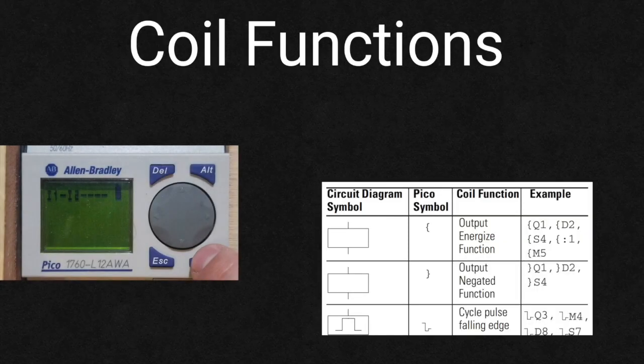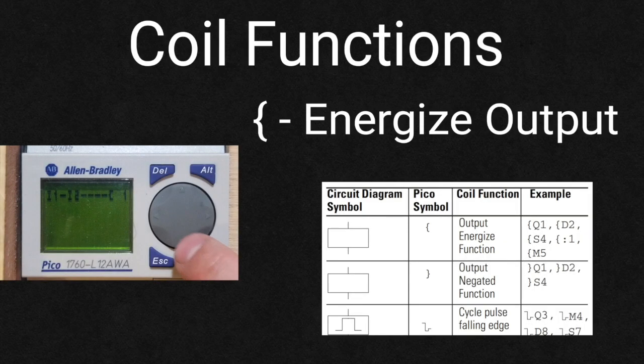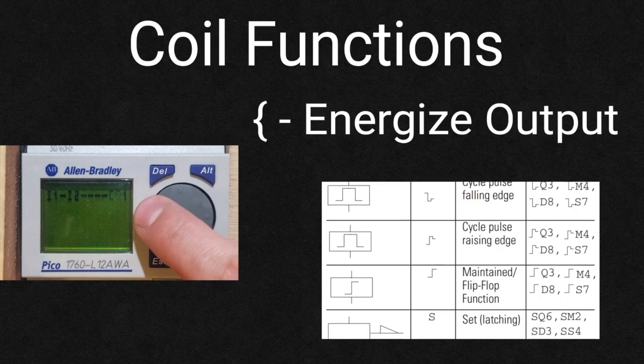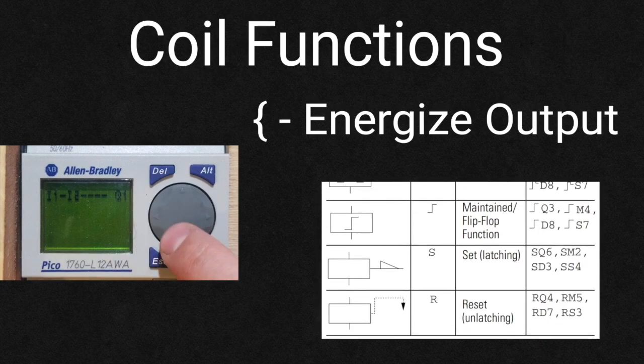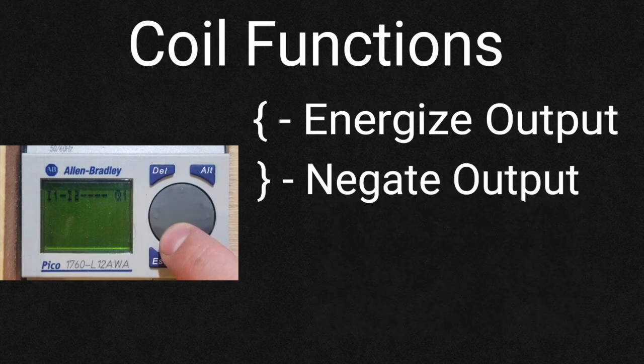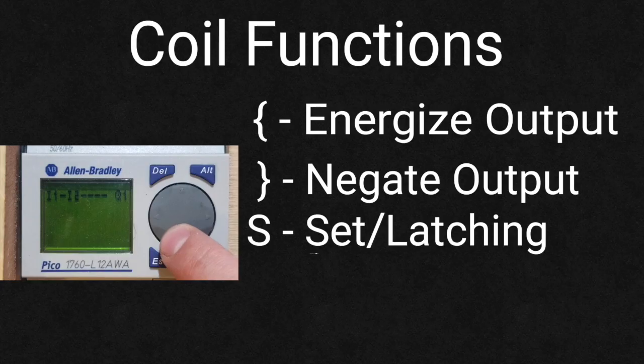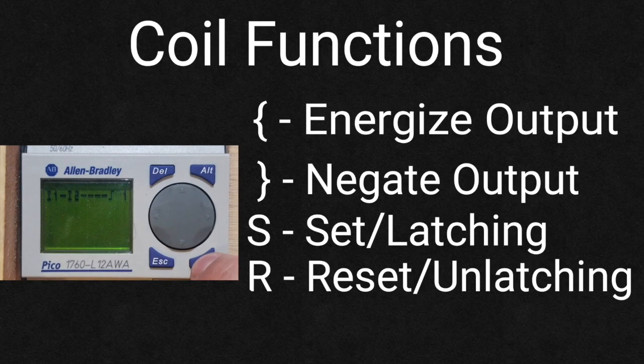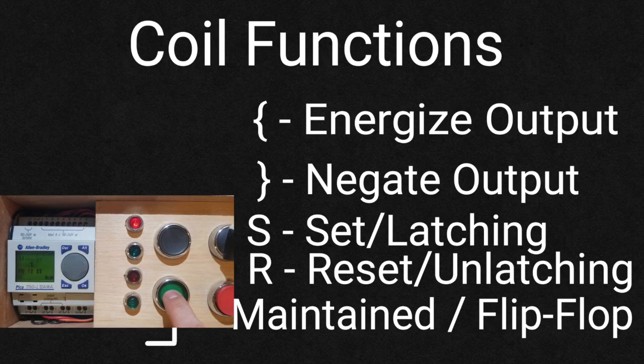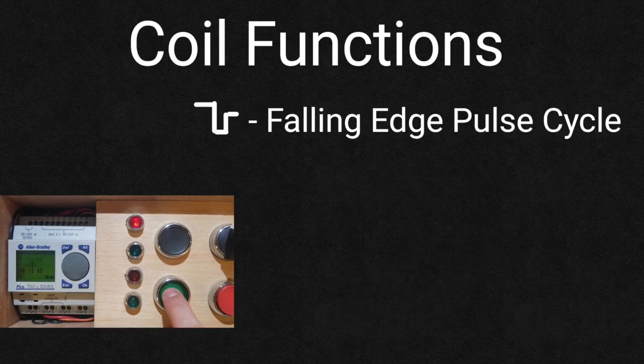There are seven coil functions available. Classical relays use the energize output type. There's also a negate output and a set and a reset function. Use relay functions S and R only once per relay. If both coils are triggered at the same time, priority is given to the coil further down in the circuit diagram, and a flip flop function.